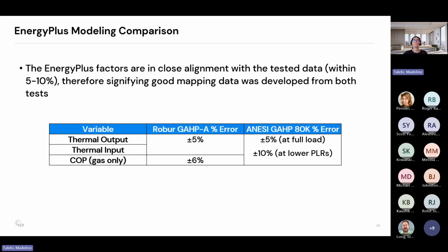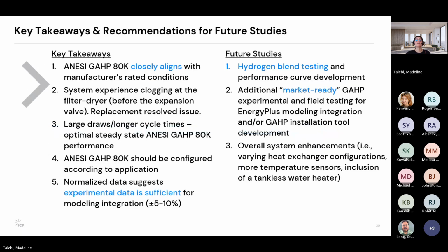And then looking at that modeling comparison, as I mentioned, for the ANESI at full load, 5% plus or minus, 10% plus or minus at the lower, and then the Robur was in alignment with an agreement within those types of margins of error. So that was, again, a positive finding. To summarize some key takeaways: the ANESI overall closely aligns with the manufacturer's rated conditions. The system did experience clogging at the filter dryer, right before the expansion valve, due to some of the refrigerant, and a replacement ultimately did resolve that issue.